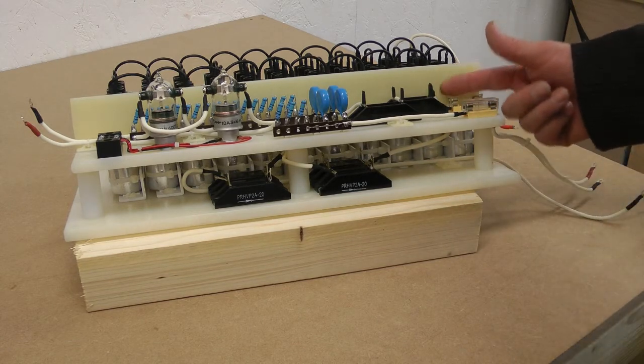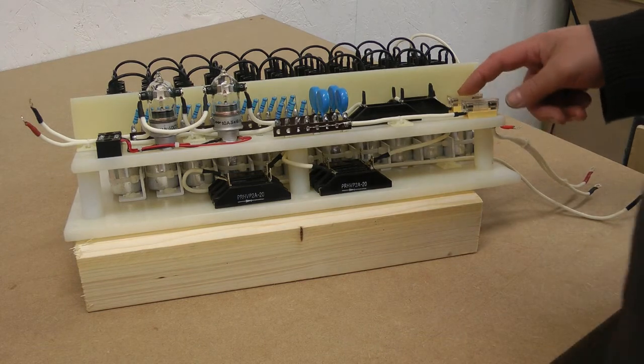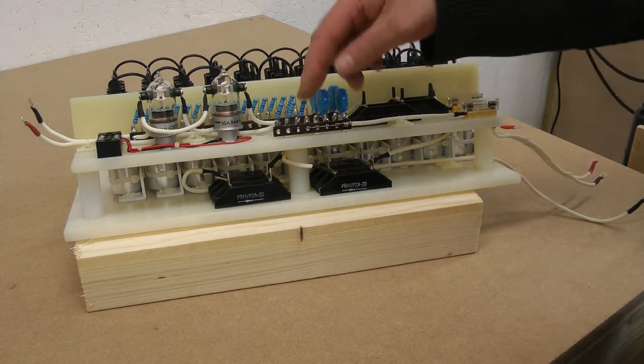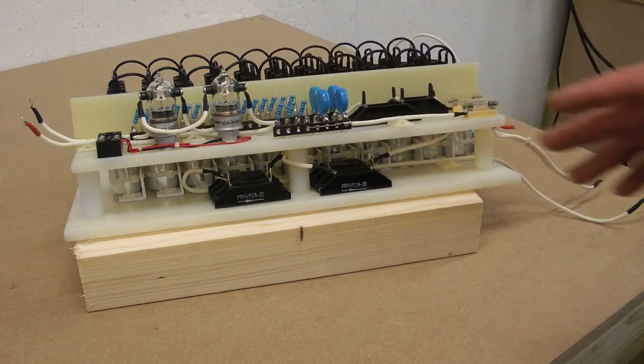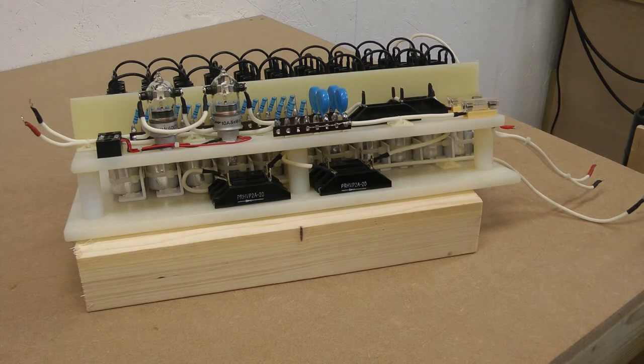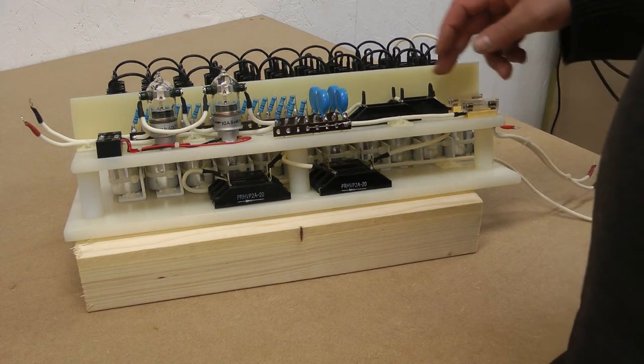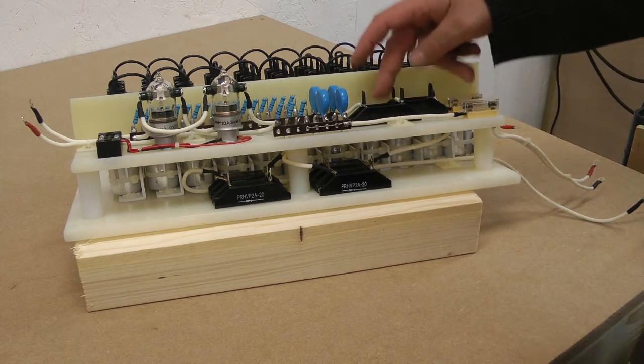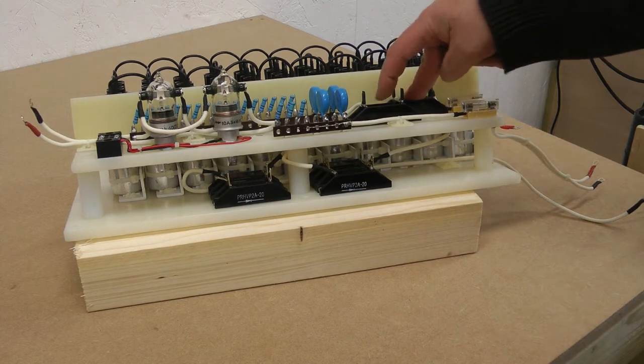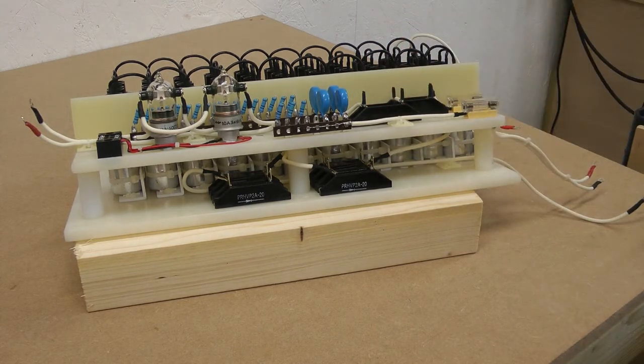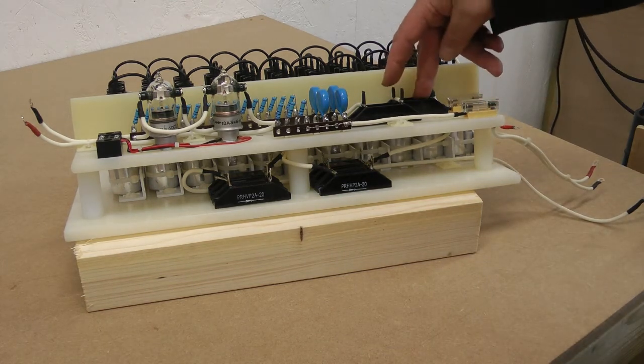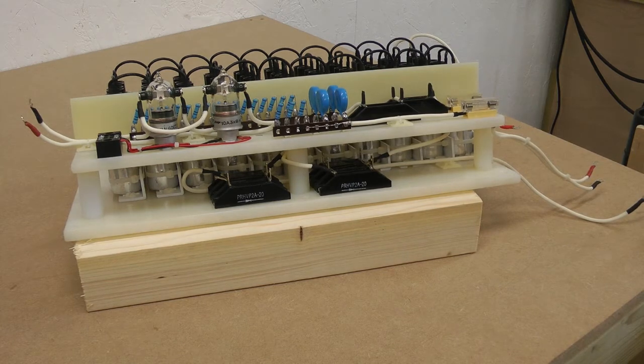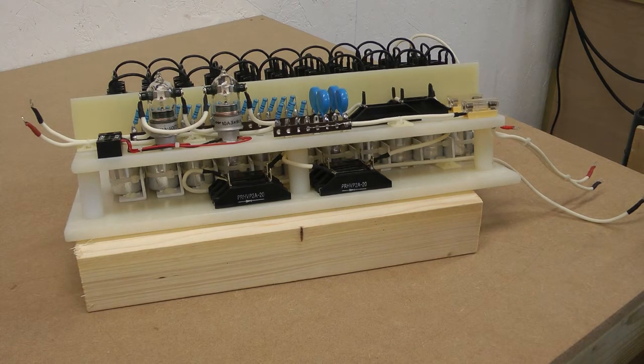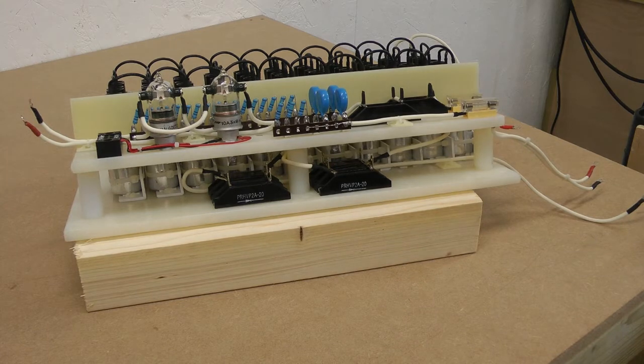That incoming, again, we've got a fuse down here, just in case, because this is connected directly to the output. If there were any arc over in any of these components, either down to the low voltage, to earth, or to another part of the circuit, then we could end up with a tank capacitor charged up on the output. We could end up with enormous discharge currents through these semiconductors, which I have had that situation before. I didn't used to have fuses here originally, and I did end up in that condition, and one of these semiconductors just blasted to pieces, which is both very loud and not very fun. And these are Bakelite cases, and they tend to throw Bakelite pieces all over the place.